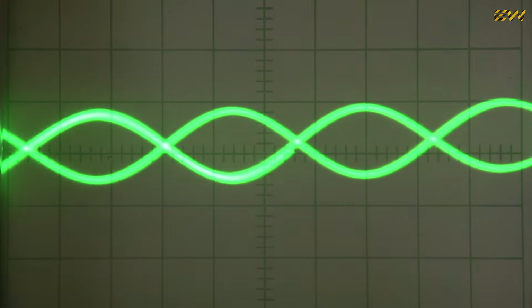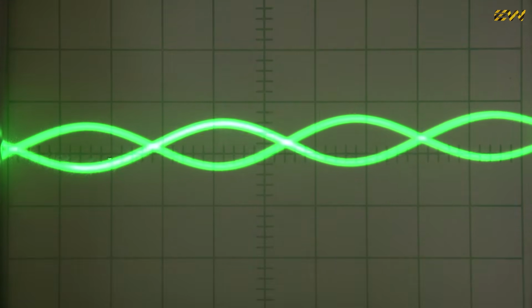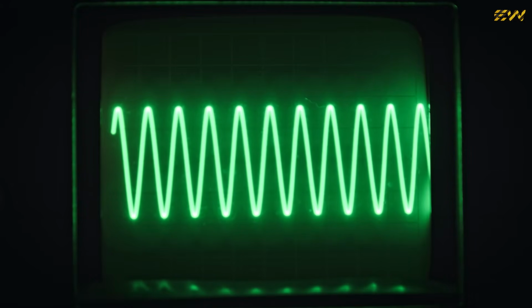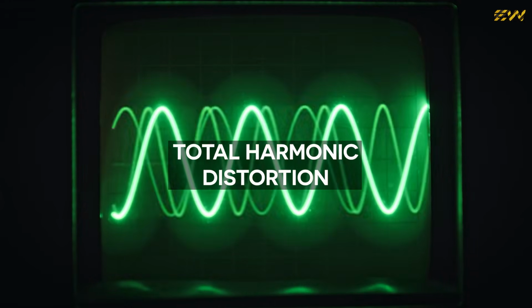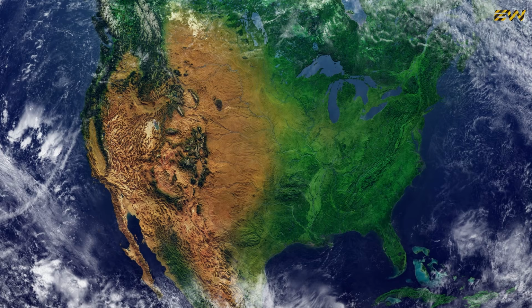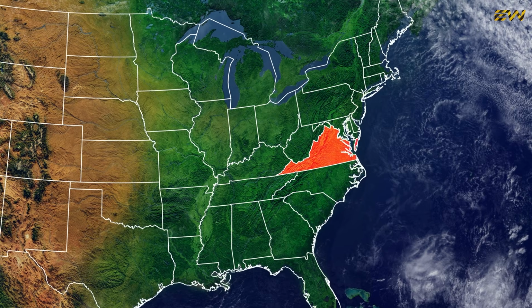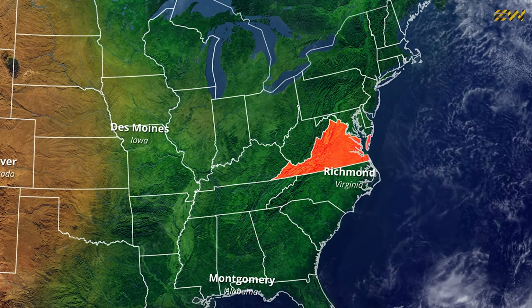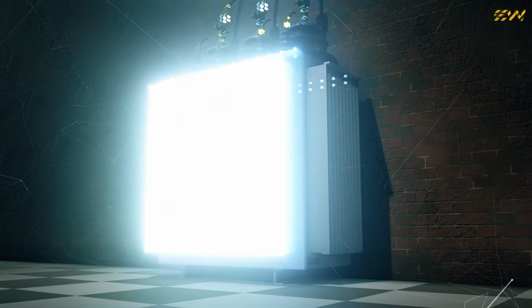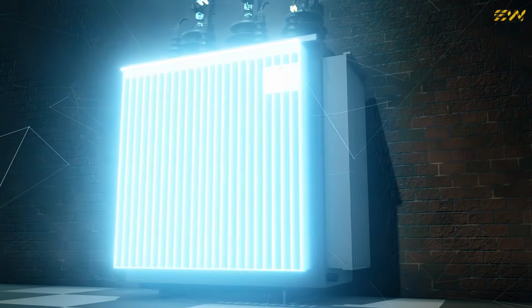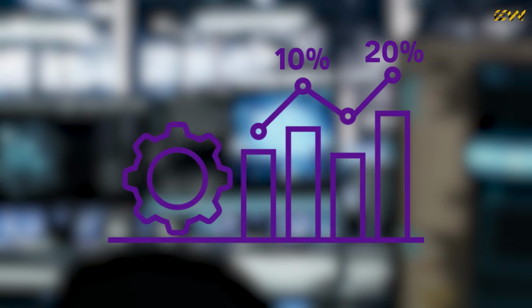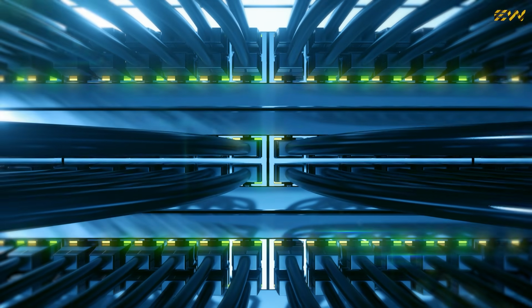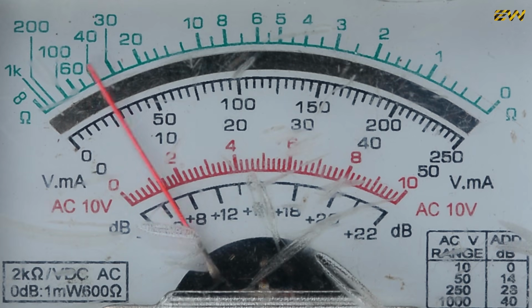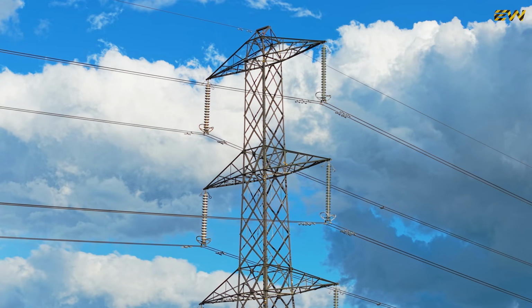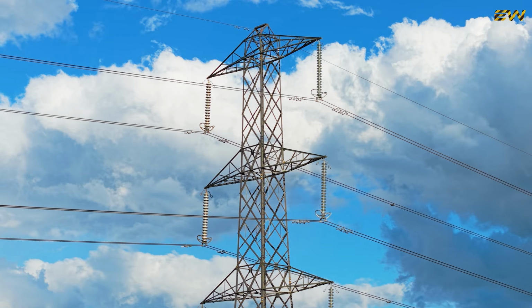Harmonics and power quality. There's another issue. Harmonics. Power electronic converters generate third, fifth, and seventh harmonics. Total harmonic distortion, or THD, can exceed 5%. In parts of Loudoun County, Virginia, over 6.8% of homes recorded monthly readings above 8% THD. That level can overheat transformers and damage appliances. And AI workloads fluctuate rapidly. Power demand can swing by 10 to 20 megawatts in under a second. In weak distribution networks, that causes voltage flicker of plus or minus 5 to 10%. The grid was not designed for this level of dynamic electronic load.